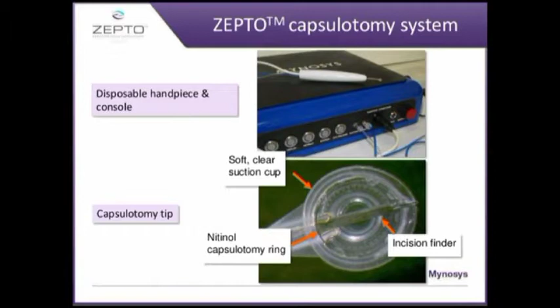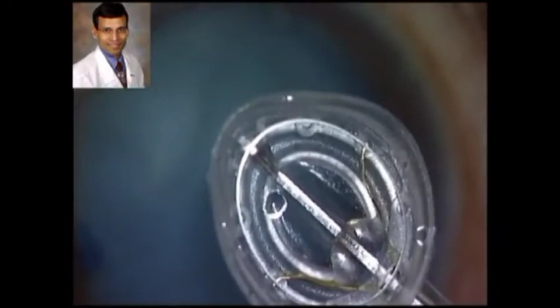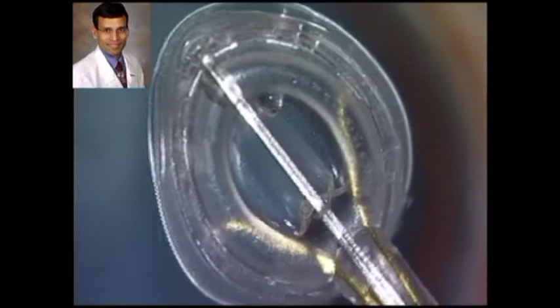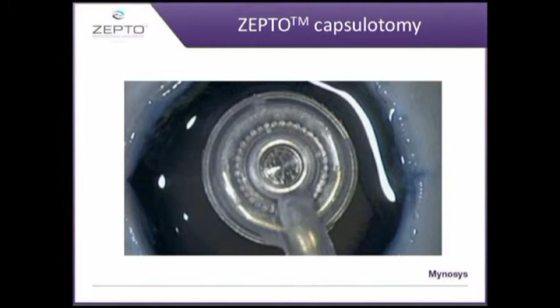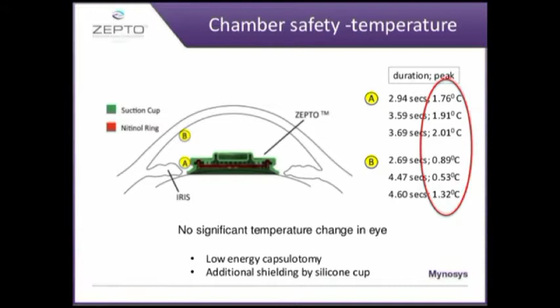So this is the basic device with a console and a handpiece. The handpiece has a silicone suction cup with a nitinol ring. Nitinol is a nickel titanium alloy, which is a shape memory alloy, which means that whatever shape it is bent into, it always comes back into its original position and shape, and therefore it is very useful for creating uniform capsular rhexis. Studies have also been done to evaluate the temperature increase during the procedure, and it has been found that there is negligible increase in the temperature while creating these capsulotomies.